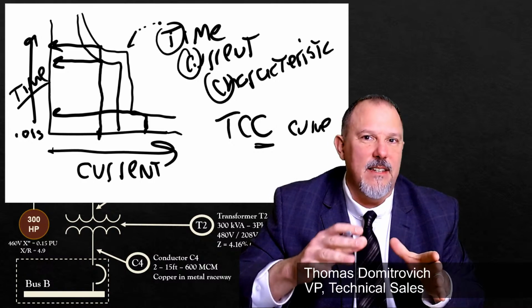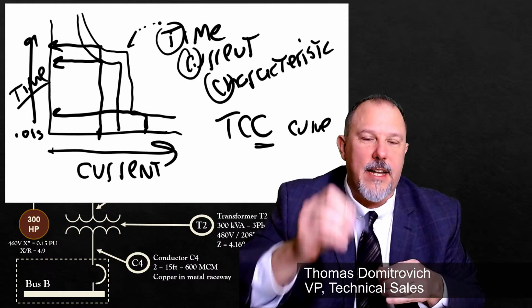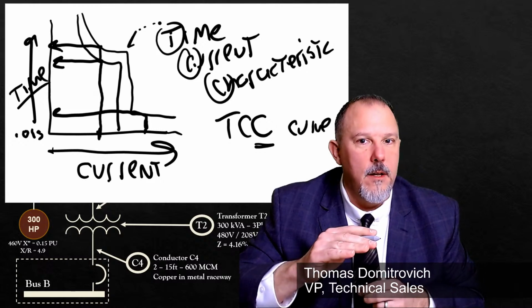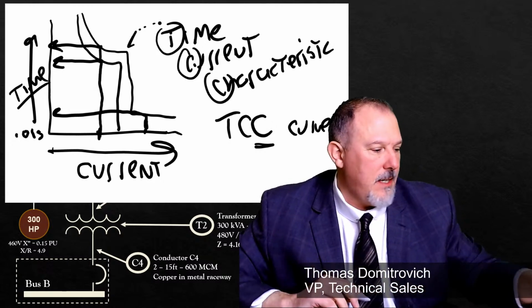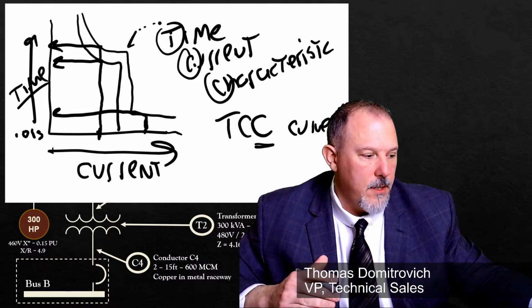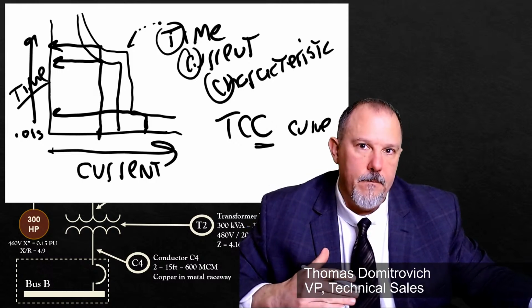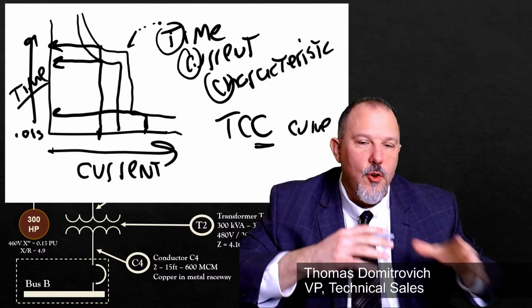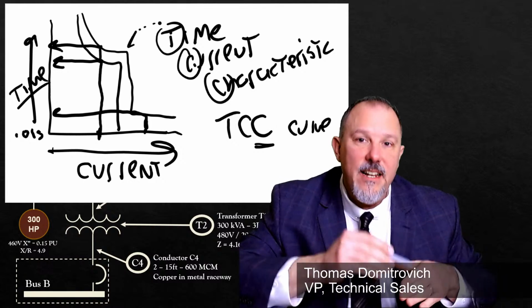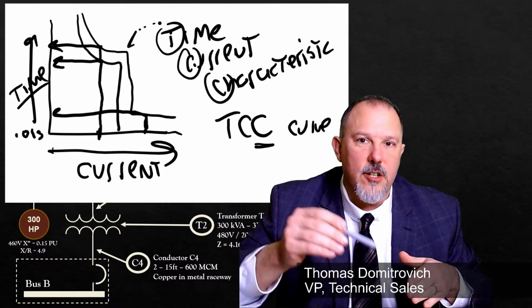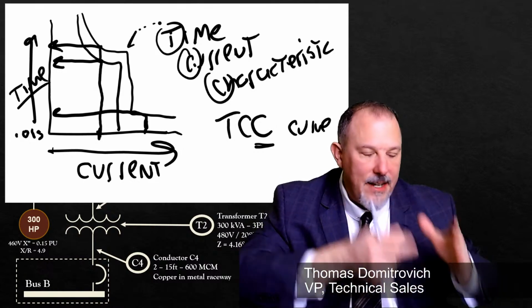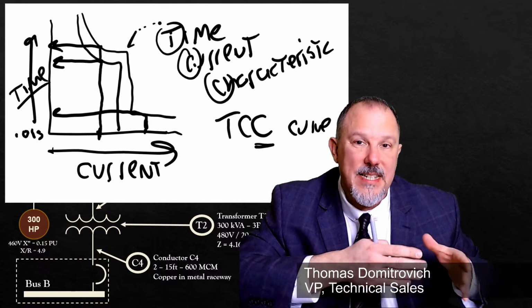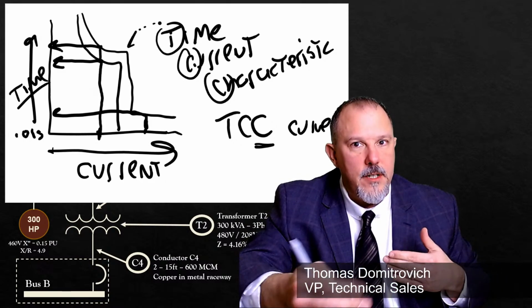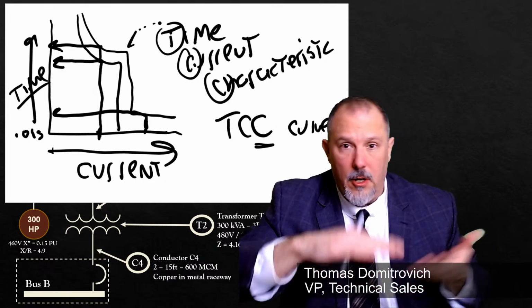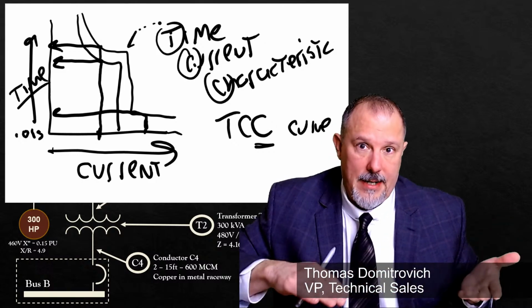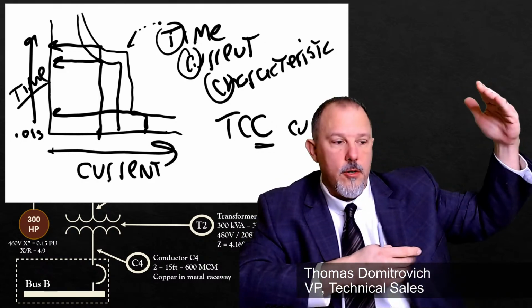We're talking about the TCC curve, the time current characteristic curve. We don't mess around with the C's in TCC. So the higher the fault current, the faster the clearing time. And you know what we call that? An inverse time current characteristic curve. So it's an inverse TCC curve. And the reason we say inverse is the higher the current, the faster the clearing time. The lower the current, the longer the clearing time.